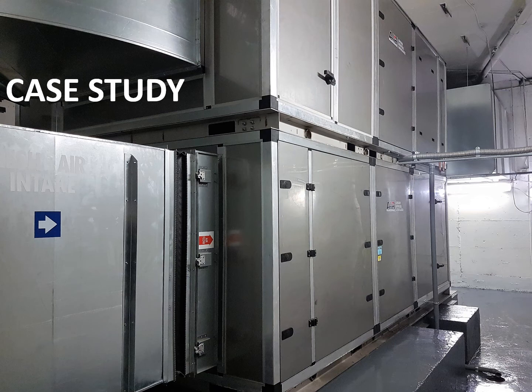And the challenges of passive heat recovery are things such as fouling of the heat exchangers. We have defrost concerns. In the example of heat wheels, the heat wheel needs an air purge cycle to clean itself as it rotates from one airstream to the other. All these things reduce efficiency and are difficult to represent on paper. So I really like using real world data as a comparison of different technologies.